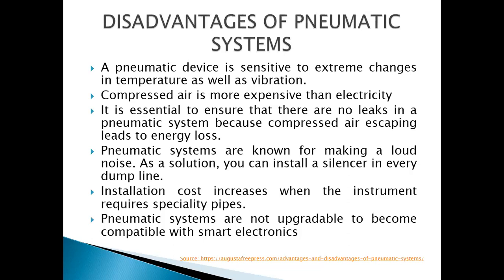As a solution, we can install a silencer in every dump line. See, we are using a compressor for compressing the air. So as and when we use a compressor, there is noise. So either we have to use a silencer, or in industry what we are doing, we are making a compressor division, and we keep all the compressors in a single room which is far away from the assembly lines or from the point where workers are doing work. So with the help of pipeline, we supply this compressed air.